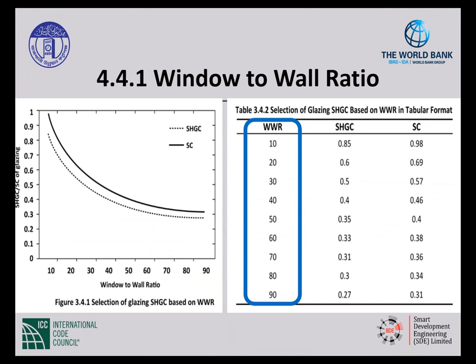First, for windows. In section 4.4.1, it tells us that for mechanically ventilated and cooled buildings, all occupancies except hazardous and storage, the window to wall ratio of the building will be determined in conjunction with the glazing performance, the solar heat gain coefficient, and the shading coefficient of the glass we use. So there's this relationship between how much glass we use and what kind of glass we use. This is shown in the table in figure 3.4.1 in the code. How much window to wall ratio do we have? How many windows do we have in our wall? What's the area of that? And here's our solar heat gain coefficient.